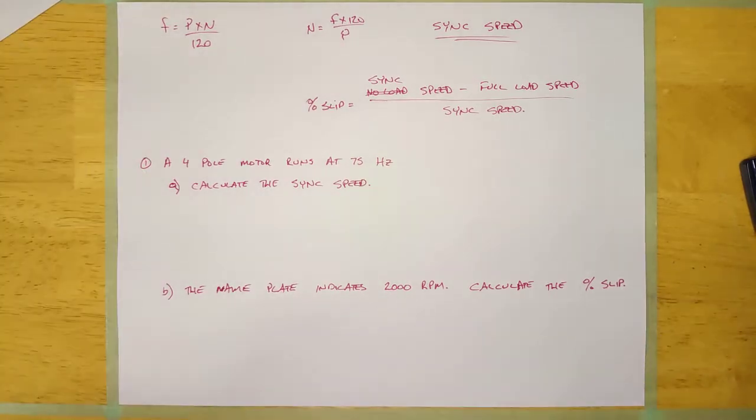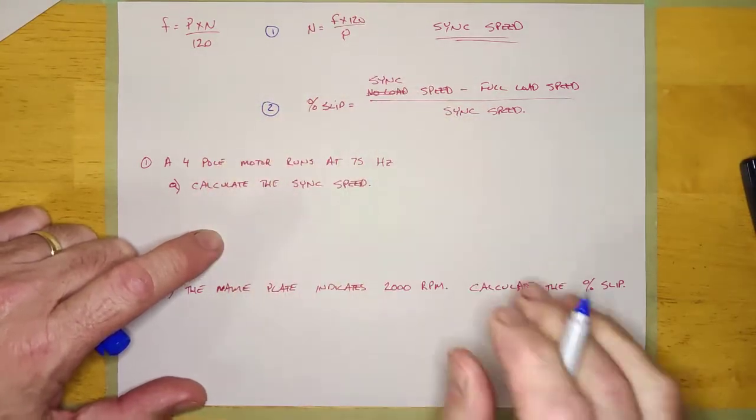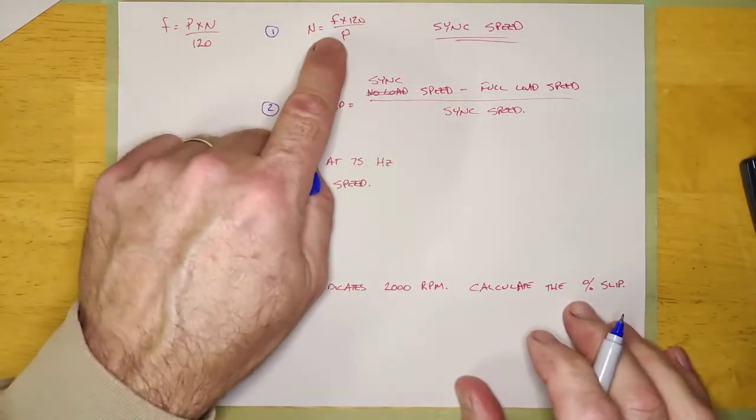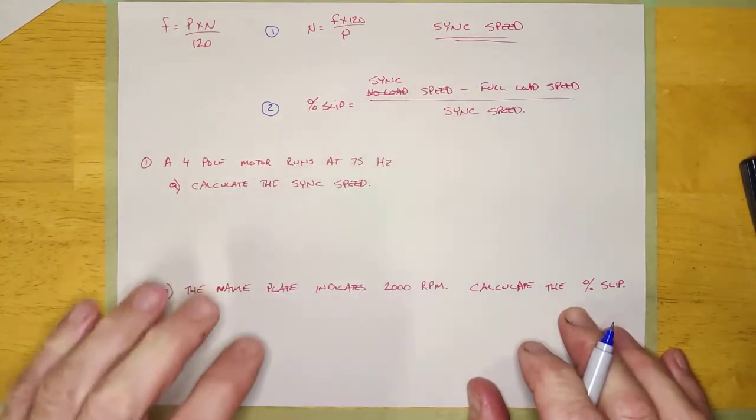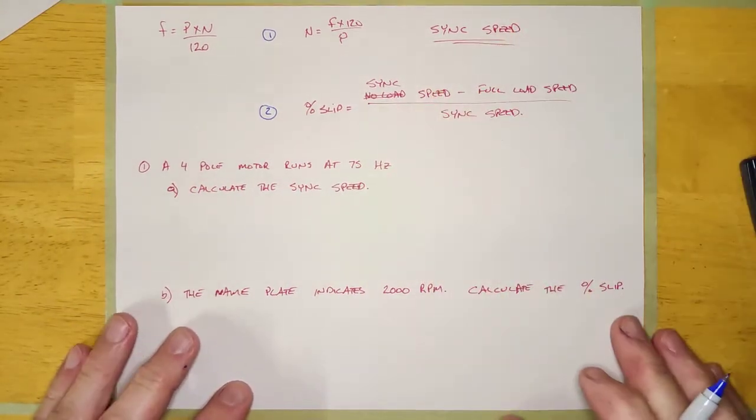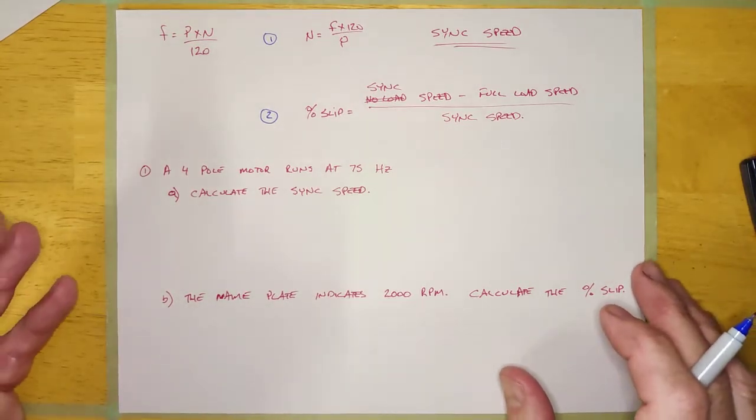There's only two. You've done both of these formulas before, I'm pretty sure. If you've had electronics at least. If you haven't, we're going to talk about them right now. So the two formulas that I want to talk about are these two right here. Now, this formula here, n is equal to f times 120 over p, what that allows you to calculate is the sync speed of a motor if you know the frequency and the number of poles.